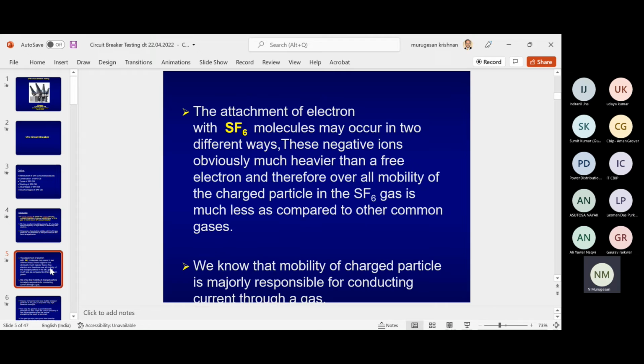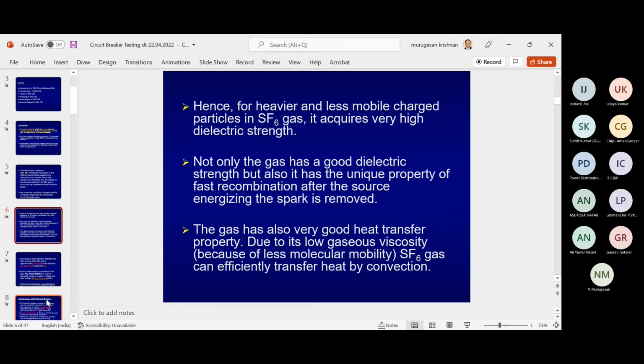The attachment of an electron with the SF6 molecule may occur in two different ways. The negative ion is obviously heavier than the free electron, and therefore the overall mobility of the charged particle in SF6 is much less as compared to other common gases. Hence, with heavier and less mobile charged particles, SF6 gas has high dielectric strength, and the arc is quenched.